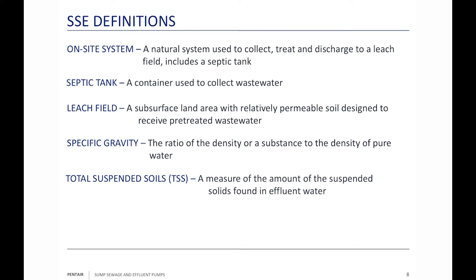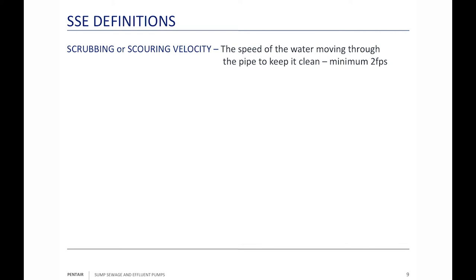Scrubbing or scouring velocity is the speed of water moving through the piping system to keep it clean, with a minimum of two feet per second. In a fresh water system, slower is fine, but when moving water through a sewage system you want at least two feet per second. That velocity helps scour or scrub the sidewalls inside the pipe so stuff doesn't cling and plug it up.